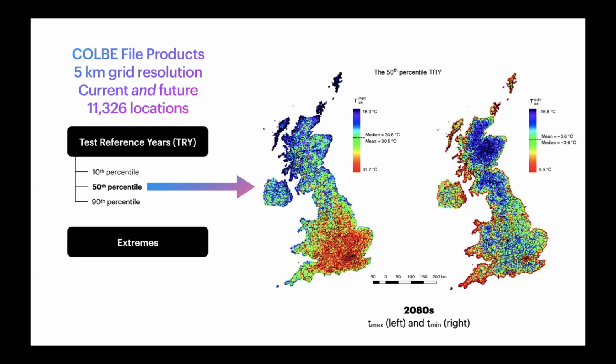In addition to these 3 weather files using standardized methodology, test reference year, you also get some descriptions of extremes. You get design summer years, which are sort of the 3rd warmest year in a period. So it's the median of the upper quartile. I think Nishesh alluded to these in his presentation. You get something called the supersynthetic heat wave.